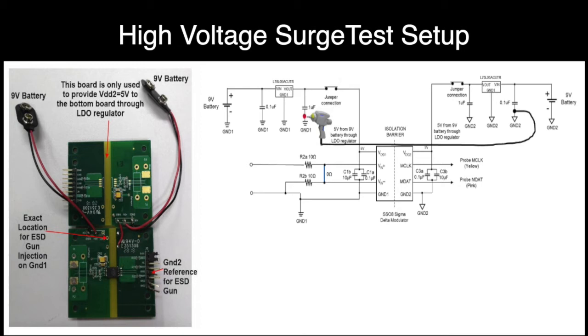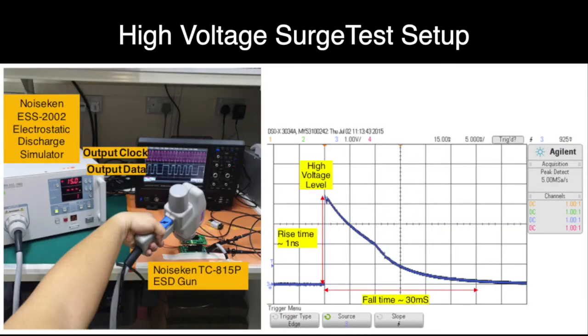I've prepared evaluation PCB boards with 2 isolated sides. Both primary and secondary sides of the PCB are powered by 9-volt batteries separately. The 9-volt is converted to 5-volt on each side of the PCB to power up the sigma-delta modulators. The differential inputs of the sigma-delta modulators are shorted to primary side ground. An ESD gun is used as the source for high-voltage surge. The ESD gun has a surge profile of very fast rise time of less than 1 nanosecond and a slow fall time of about 30 milliseconds.